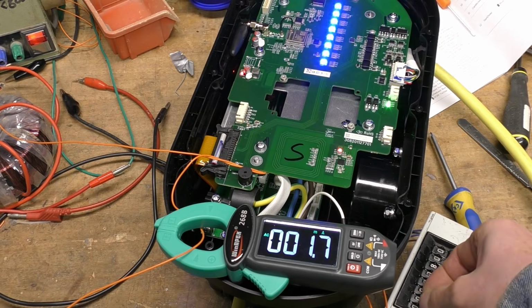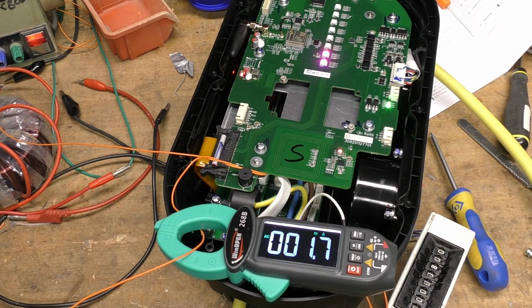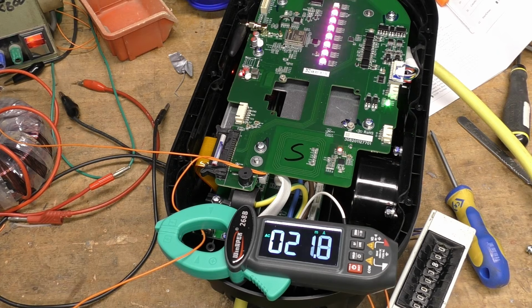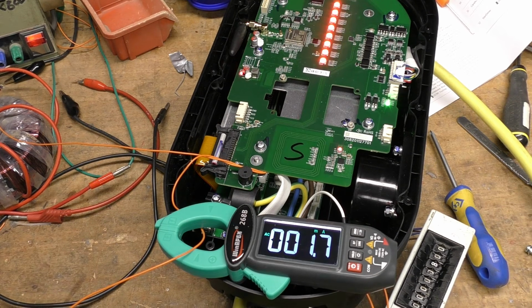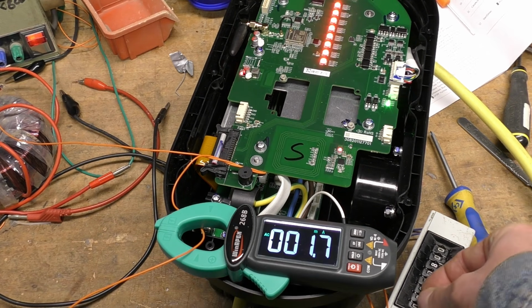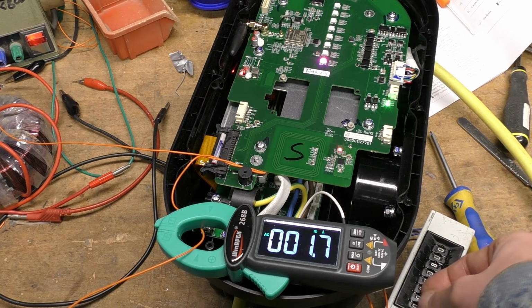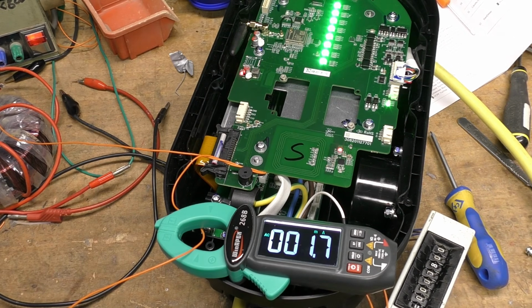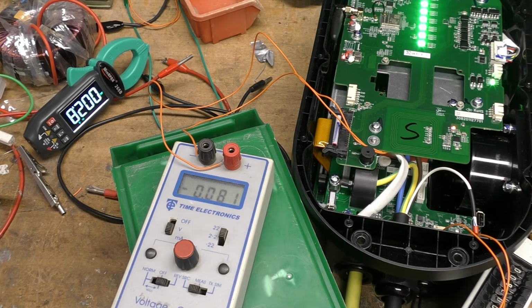Let's make it think there's a car connected, so it should trip out. Again, 25 milliamps. That stays in the fault condition until we disconnect the car, then reconnect it, which is fine. And let's just check that it will trip on a DC leak.